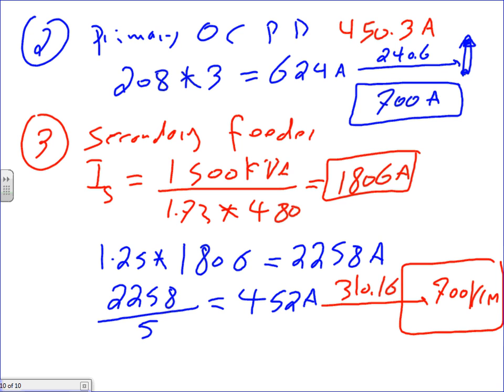How many conductors? I'm going to carry full neutral, so 4 conductors. Now, I want to bring to your attention that this calculation will change when I start putting in a panel. If I land these cables in a panel to feed a panel, then my cables have to match the overcurrent device in the panel. I'm not landing in a panel. It could be a piece of equipment that's fed from all this power. Otherwise, remember how after 800 amps you start matching the cable to the overcurrent device?